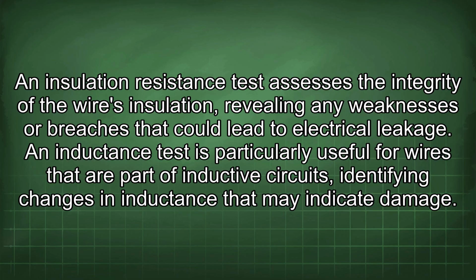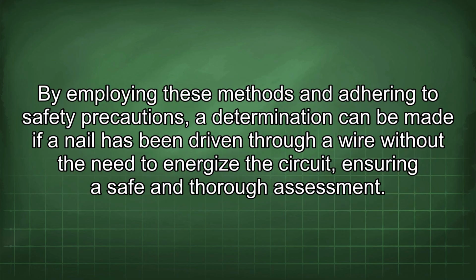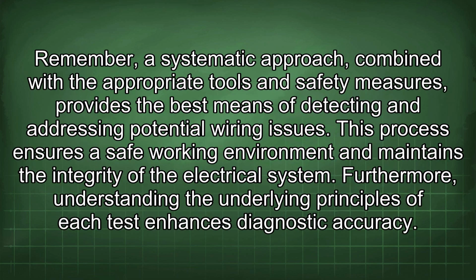An inductance test is particularly useful for wires that are part of inductive circuits, identifying changes in inductance that may indicate damage. By employing these methods and adhering to safety precautions, a determination can be made if a nail has been driven through a wire without the need to energize the circuit, ensuring a safe and thorough assessment. Remember, a systematic approach, combined with the appropriate tools and safety measures, provides the best means of detecting and addressing potential wiring issues. This process ensures a safe working environment and maintains the integrity of the electrical system.